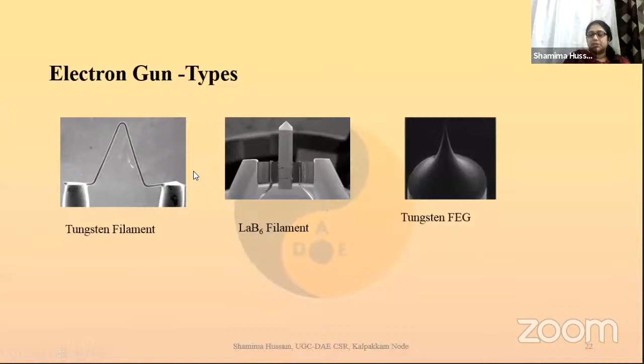So when we talked of this tungsten or this LaB6, what we were talking of was thermionic emission. We all know what thermionic emission is. The filament would be tied here, and we would be putting some kind of heater to heat this filament. Somehow we made the connections here, and then when it is heated, as if you remember our old days incandescent bulb, we used to have that kind of coil, right? When we would switch it on, the filament will glow and the room gets illuminated. Even now, sometimes if there is a low voltage, you can see the filament actually glowing. In some heaters also we have it in a home. Similarly, here we had it.